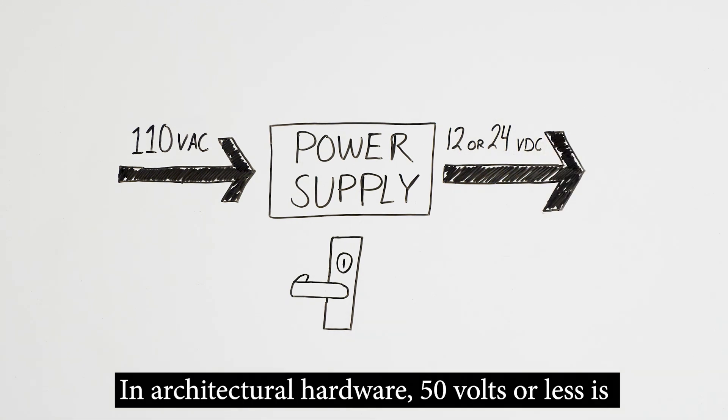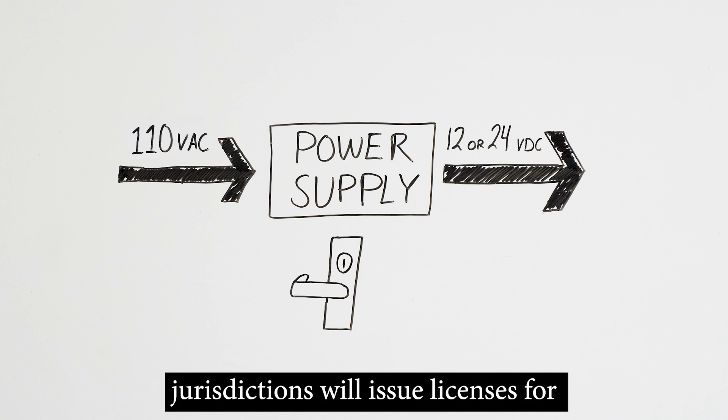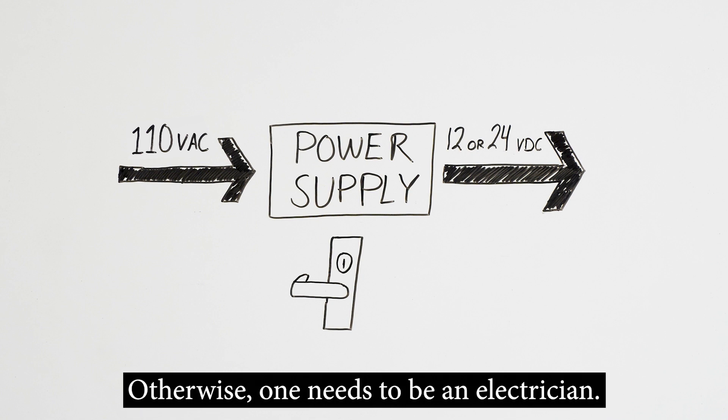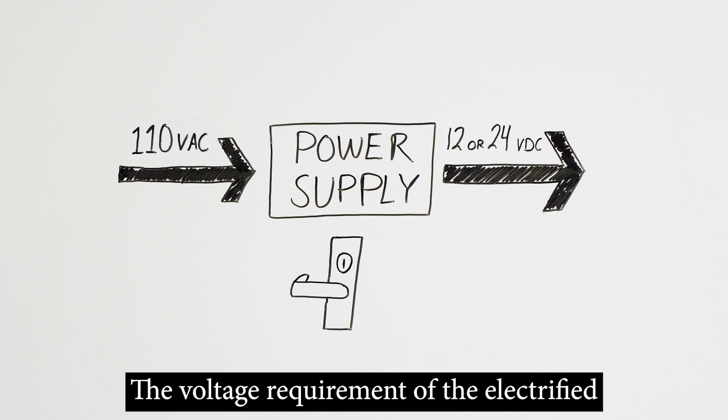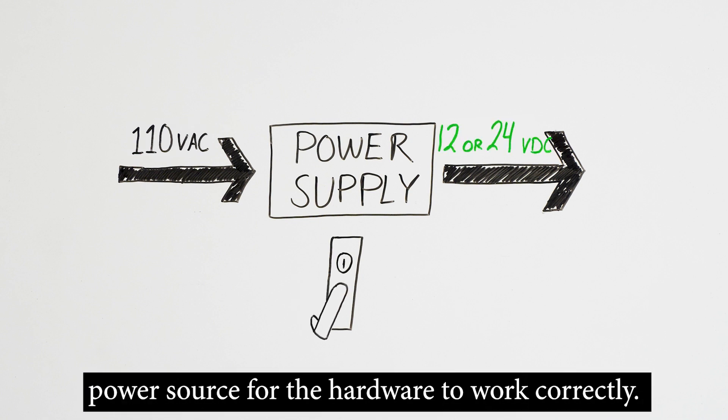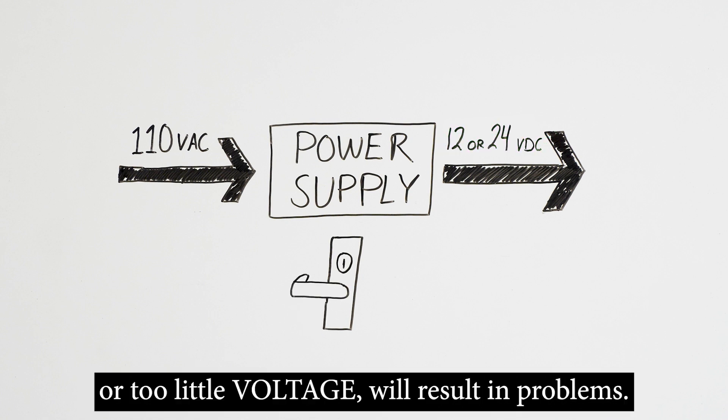In architectural hardware, 50 volts or less is considered low voltage, and some states and jurisdictions will issue licenses for individuals to work on 50 volts or less. Otherwise, one needs to be an electrician. The voltage requirement of the electrified hardware must match the output voltage of the power source for the hardware to work correctly. Too much or too little energy, that is too much or too little voltage, will result in problems.